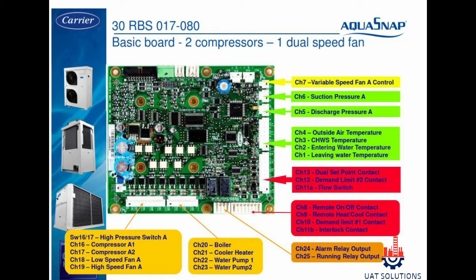Outside air temperature sensor is connected on channel 4. Chilled water supply temperature sensor is connected on channel 3. Entering water temperature sensor is connected on channel 2. Leaving water temperature sensor is connected on channel 1. Dual setpoint contact is on channel 13, and channel 12 is used for demand limit contact.